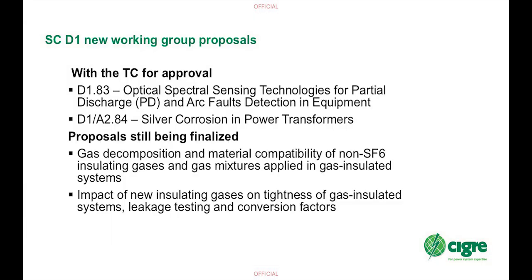D1 83 and D1/A2 84 are already approved, I checked yesterday. The first one is about how to use an optical method to test and monitor partial discharge activities, especially in GIS. The advantage of using optical methods is that they're less prone to magnetic interference, and they can be mounted in the GIS to give real-time monitoring, and they're also very sensitive to PD activities.